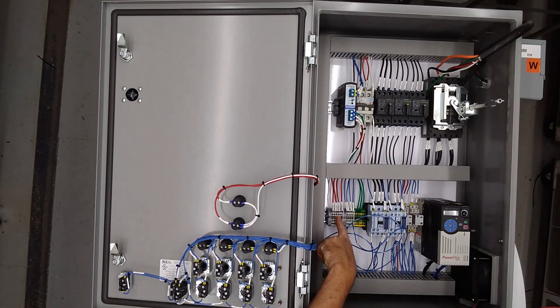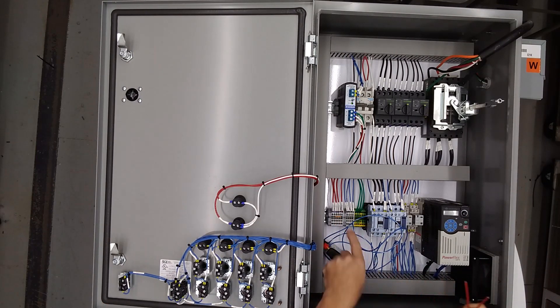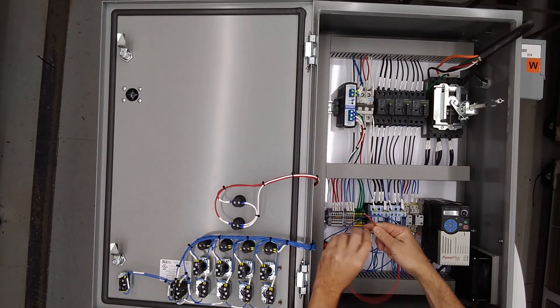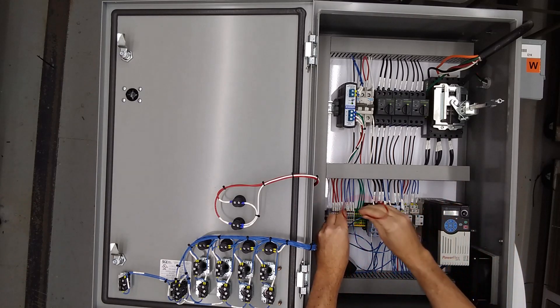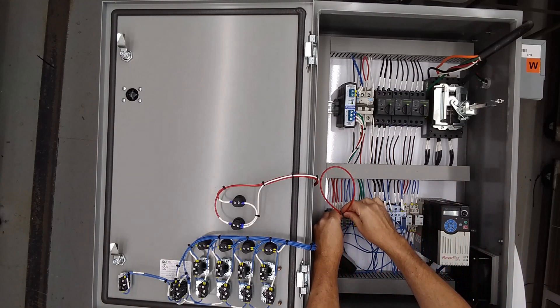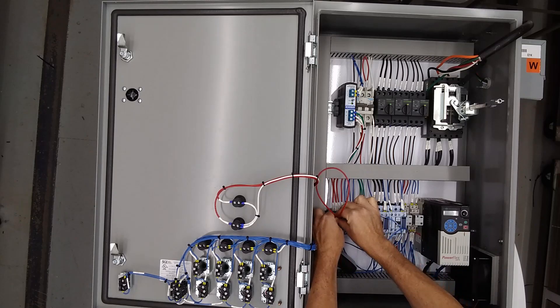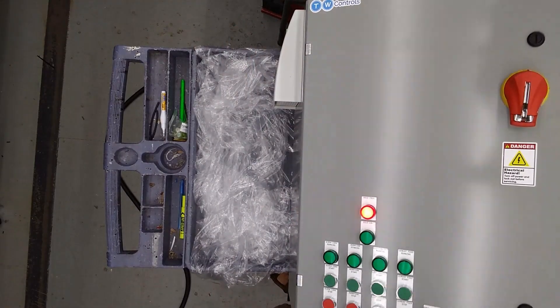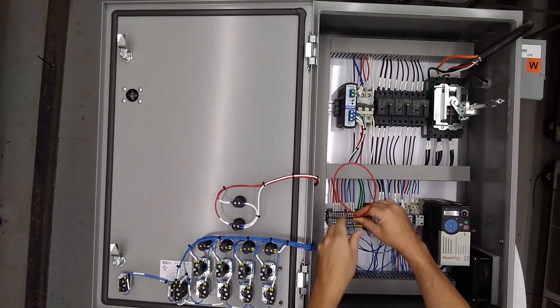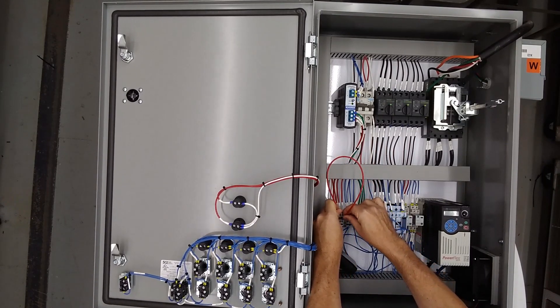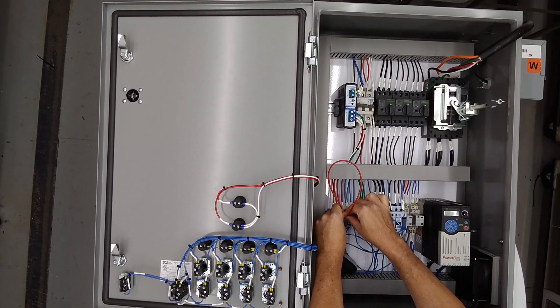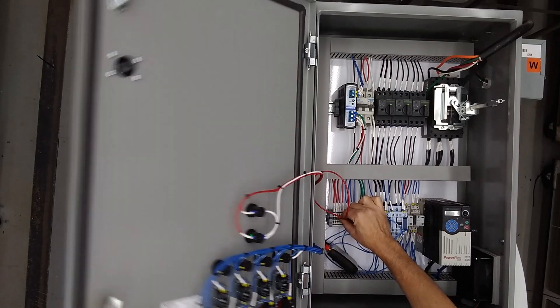Then we have our silo high and silo low indicators and that's going to be terminal three and four is one of them. So I'm going to put a jumper between three and four. And we get a silo high indicator. Then a jumper between five and six. Silo low indicator.